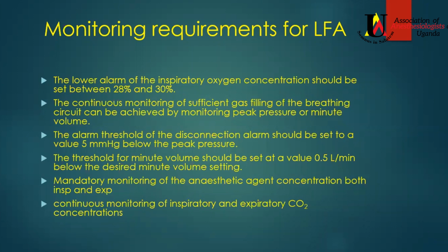Continuous monitoring of sufficient gas filling of the breathing circuit. And you can look at your peak pressures or minute volume. If you notice your minute volume is dropping, then chances are you're having a leak or you are not having sufficient gas filling your breathing circuit.